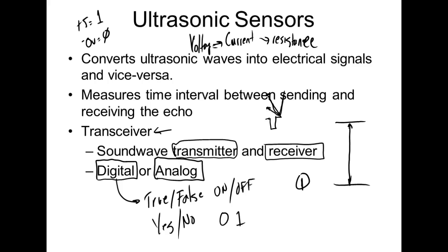So we have analog sensors and we have digital sensors. Most of our digital sensors are really analog sensors, but they run through something called an A to D converter. What we do is set what we call a threshold on them. If it exceeds the threshold, the sensor sends back a 1. If it doesn't exceed the threshold, it sends back a 0. But the actual sensing element is actually an analog sensor. Analog to digital converter.